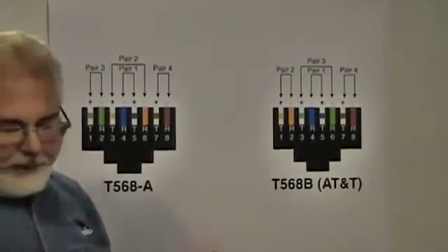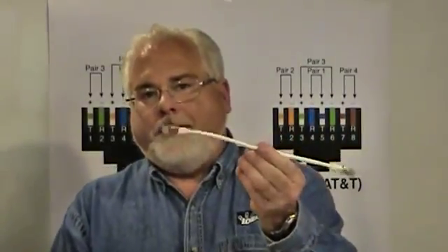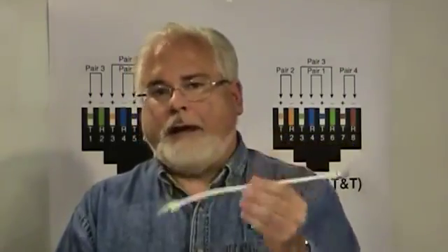And when you buy things like patch cords out there in the industry, you know, you might go down to a local retail environment and pick up a low voltage panel out of the set, and a lot of times those panels are wired in A. And in that same area, you'll find some patch cords being sold for the computers. Now, are these A or B rated? And the answer is, I don't know. Take a look at it. And more than likely, it'll be a B patch cord, because the people who make patch cords like this, they cater to data guys who are typically wiring B anyway.